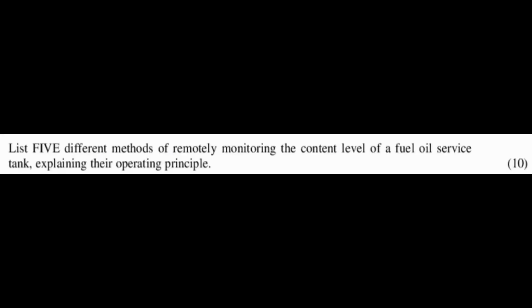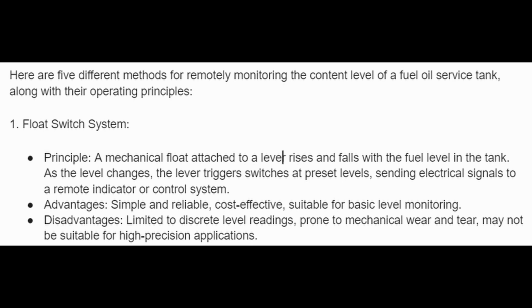List 5 different methods of remotely monitoring the content level of a fuel oil service tank, explaining their operating principle. Here are 5 different methods for remotely monitoring the content level of a fuel oil service tank. 1. Float switch system. Principle: a mechanical float attached to a lever rises and falls with the fuel level in the tank. As the level changes, the lever triggers switches at preset levels, sending electrical signals to a remote indicator or control system. Advantages: simple and reliable, cost-effective, suitable for basic level monitoring. Disadvantages: limited to discrete level readings, prone to mechanical wear and tear, and may not be suitable for high-precision applications.